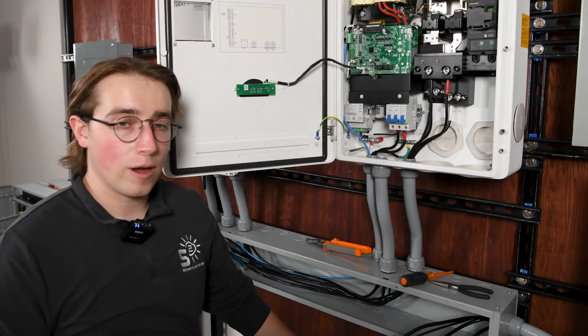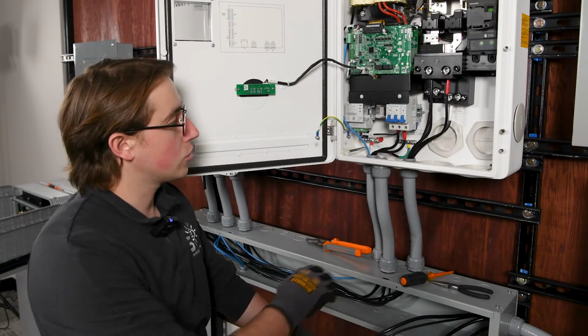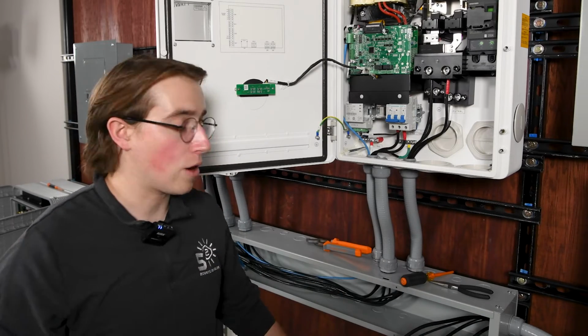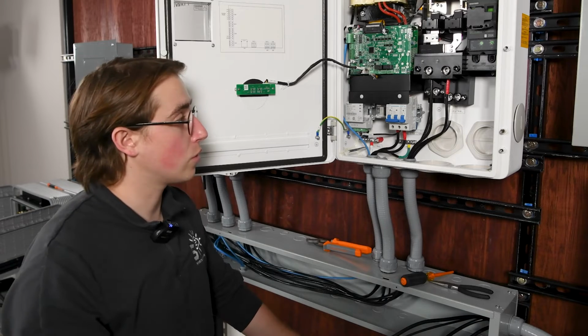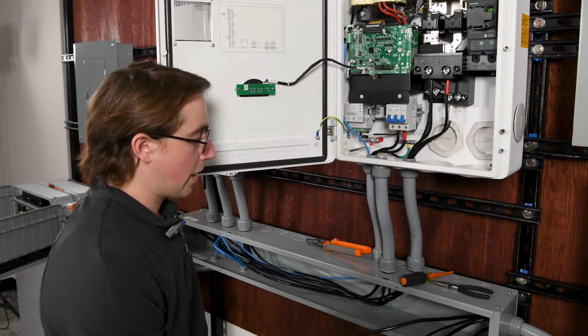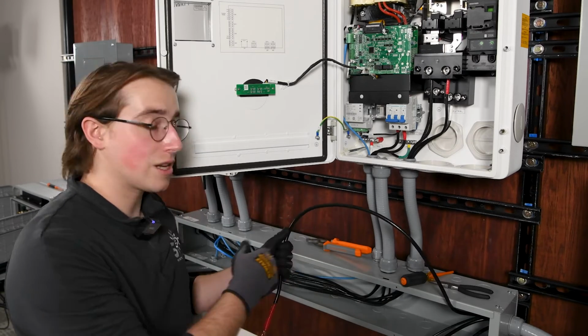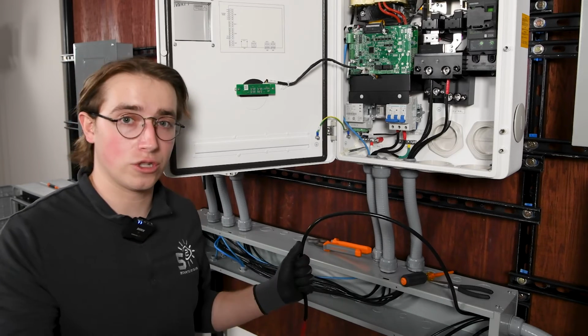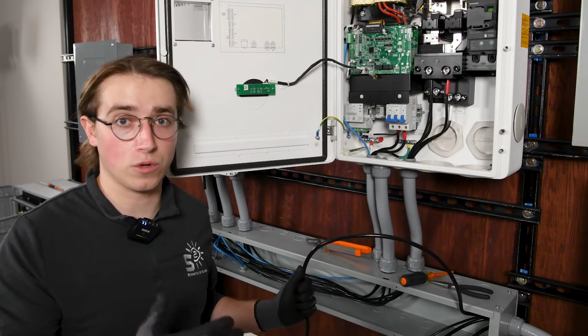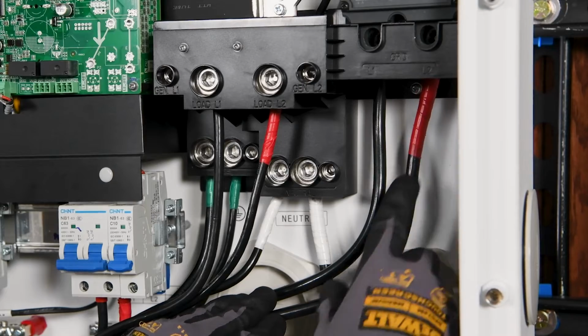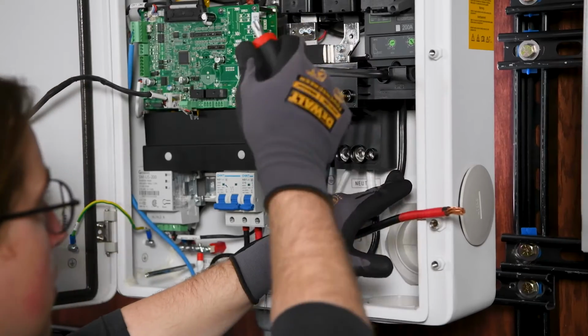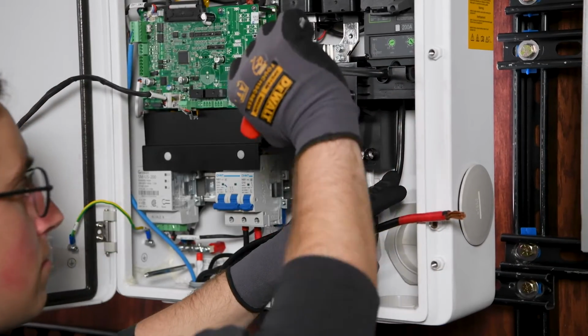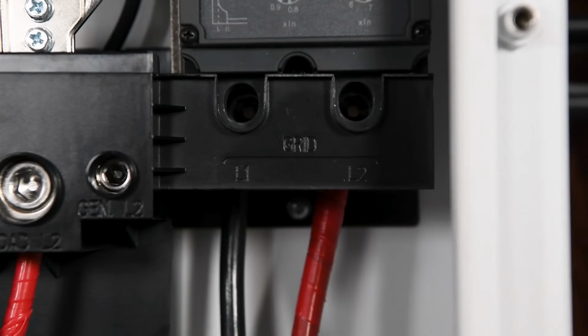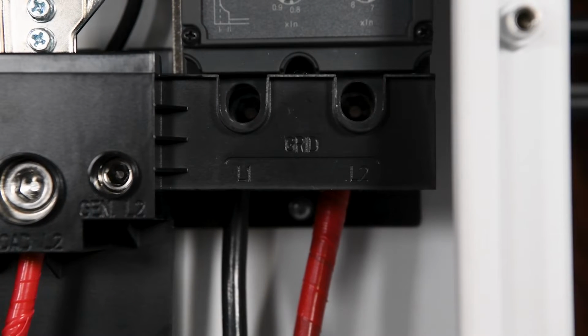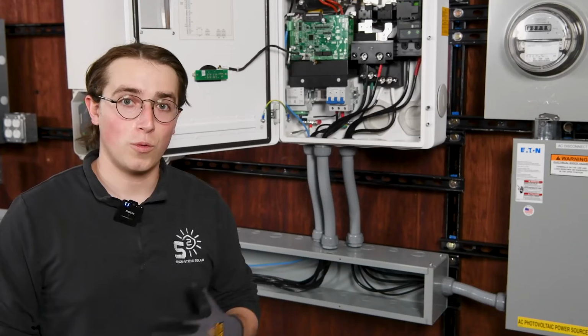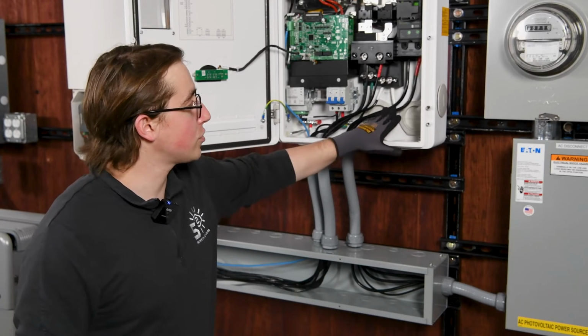Next, we're going to wire up our grid conductors to the SYN. Now, we have a 100 amp service coming in, and our conductors are going to be slightly smaller than the standard 200 amp conductors that you would see if you were doing whole home backup. We're going to wire our hot legs to the breaker input here where it says grid, L1 and L2, and our neutral and our grounds will go at the bottom here. We now have the SYN wired up to the grid connections here.